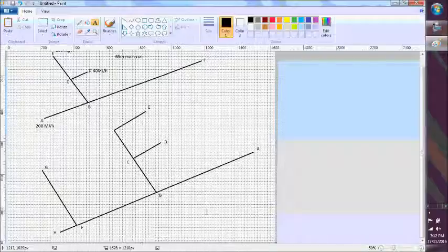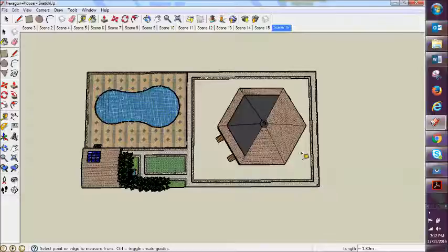Yep. That's 2.75. So that's F, going the same 6 megajoules as what we did on the first one. Yep. And then barbecues, 40. G. Yep. That's H. Okay, but the other thing that's going to change here now is our main run, because now it's not the pool heater that's the furthest away, it's the barbecue. So we got 76 plus, no, 65 plus 26, 90 metres is our main run now.